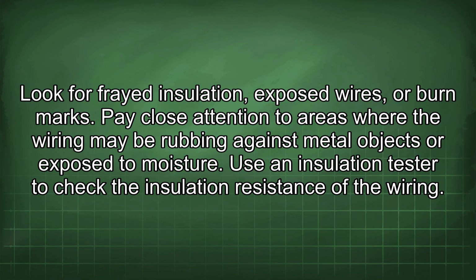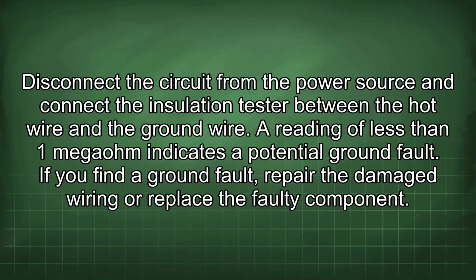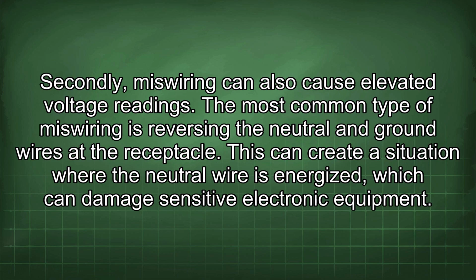Use an insulation tester to check the insulation resistance of the wiring. Disconnect the circuit from the power source and connect the insulation tester between the hot wire and the ground wire. A reading of less than 1 megohm indicates a potential ground fault. If you find a ground fault, repair the damaged wiring or replace the faulty component. Secondly, miswiring can also cause elevated voltage readings.